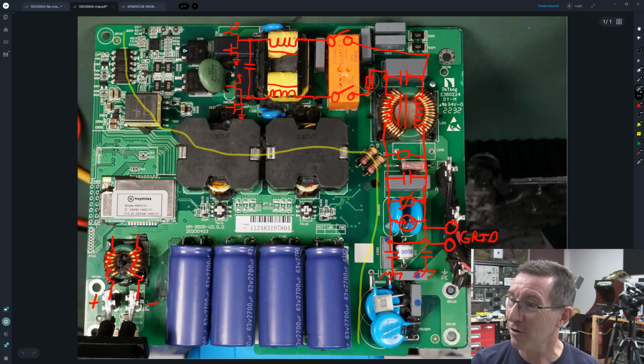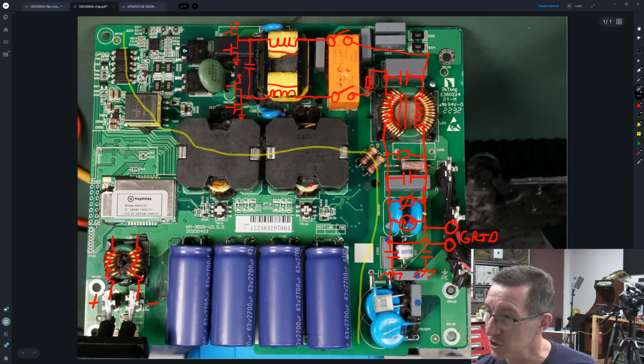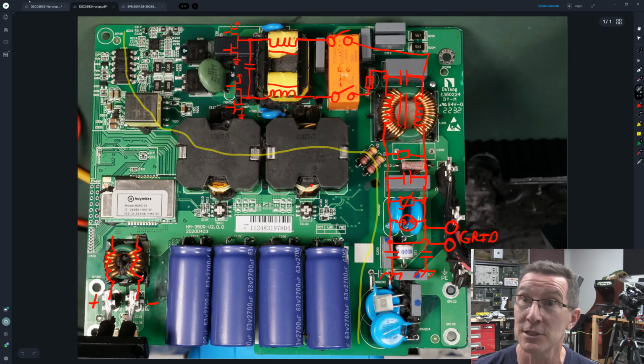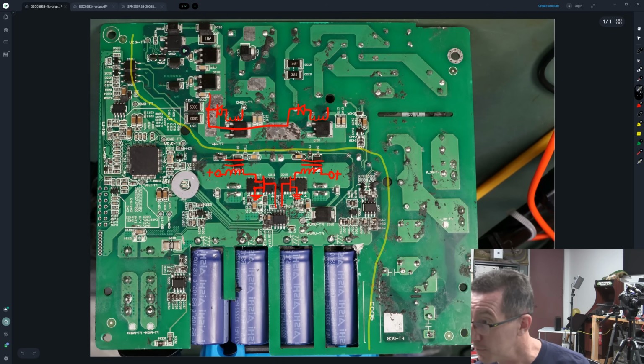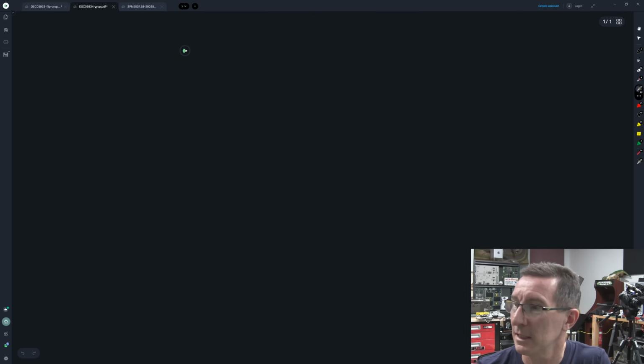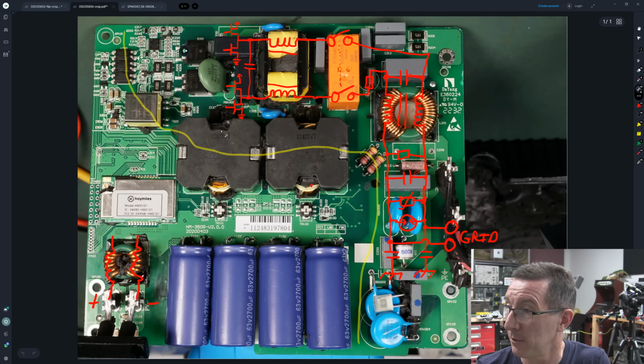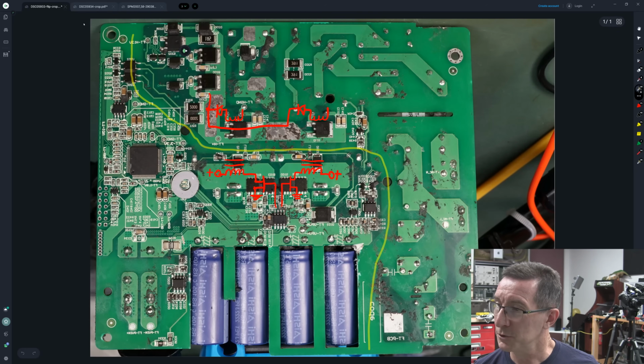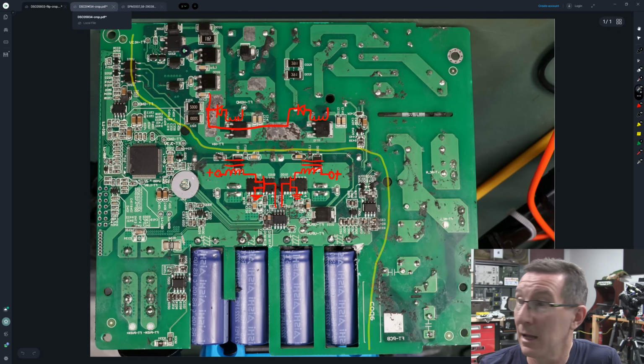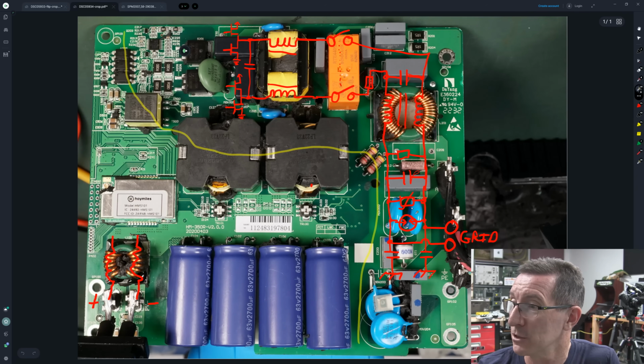Yeah, I got this wrong - the gas discharge tube is not directly across there, it's there. It's more likely in series with the MOV, and sure enough, it is in series with the MOV. If you jump over to the bottom here, the GDT is here, and then the MOV goes over like that. Yes, it is in series. In fact, you've got two identical MOVs there, is it? Anyway, you can dick around with that, but yes, I do believe the discharge tube, the GDT, is in series with the MOV there. So yeah, there you go.